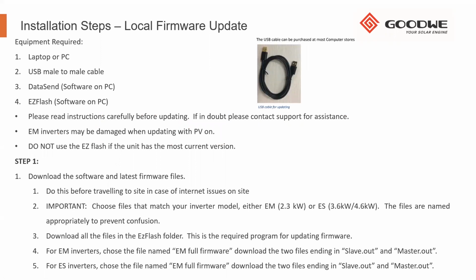Now we move over to the firmware update for the inverters. So this is a local firmware update. You can also request a remote firmware update from us. The remote firmware update is normally much easier, but it does sometimes not work on older firmware inverters and if the Wi-Fi connection is unstable. If that's the case and there's no Wi-Fi on site, the local update can be performed.